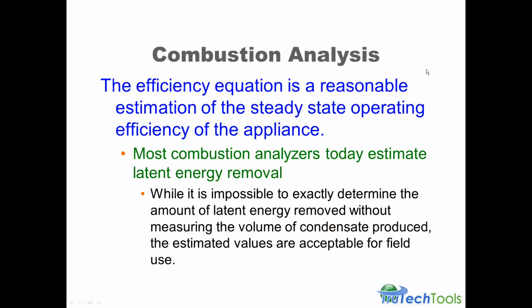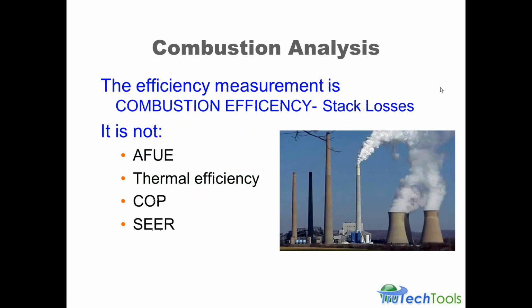So just to summarize, the efficiency equation gives you a reasonable estimation of steady-state operating efficiency. And today's combustion analyzers all estimate the condensing mode, or give you the latent energy removal that's trapped in that water vapor. If you're in the condensing mode and testing a condensing furnace, it automatically includes or calculates that. Again, we talked about not being able to tell that exactly unless you measure the volume of condensate, but these estimates that the manufacturers use are fine and acceptable for field use.